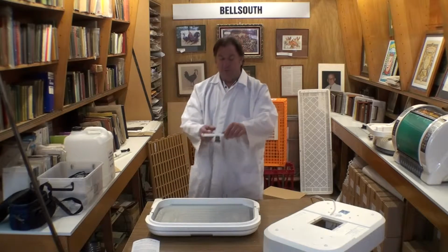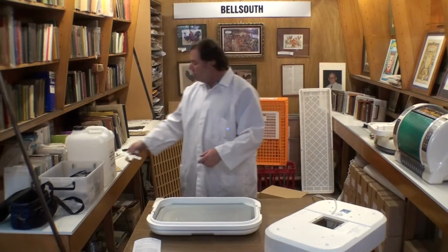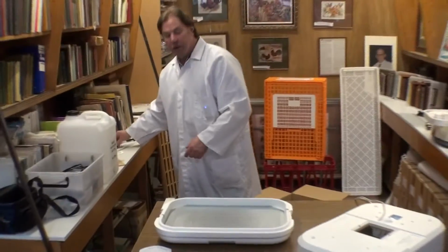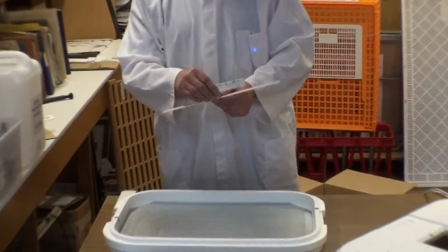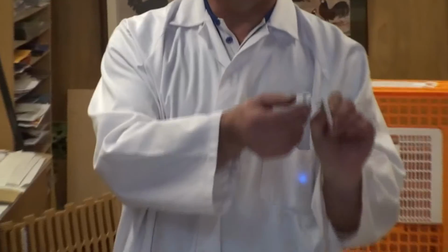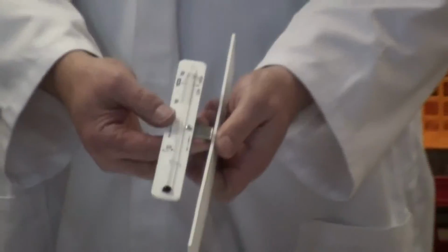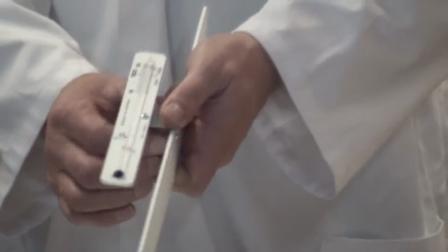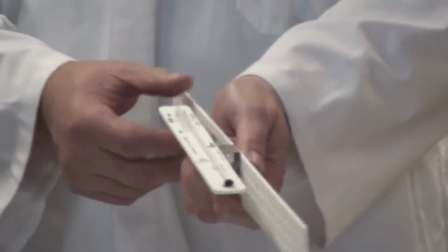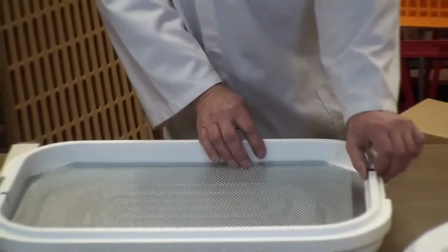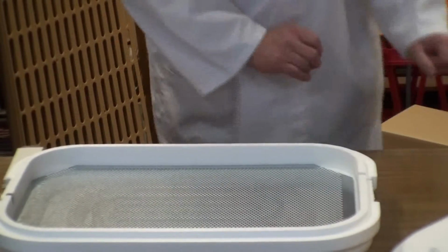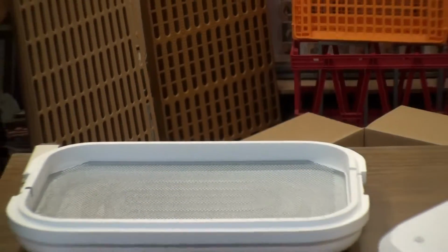You take the thermometer and you take it off this bracket and you're going to put it on a new bracket which comes in the semi-automatic turner box. And there's the new bracket mounted up on one of the tray dividers that's going to go inside the incubator. So we're going to change the sort of bracket that the machine has. There's a little bung in the end of the incubator here, and we're going to remove the little bung because that's where the turning arm is going to be placed.